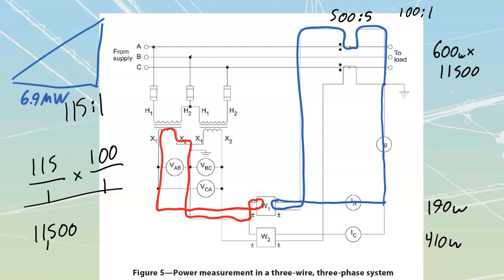Okay, now that we've got the megawatts over there, the next thing that we are going to do is figure out what our circuit power factor is. And thankfully, we have these two over here that we are able to calculate with. We can only do this calculation, though, if it is balanced. Don't try using this unless they tell you that it's a balanced load. You have to err on the side of the fact that it might not be, and you might not be able to utilize this. Because it is a balanced load, we're able to do this one where we have that inverse tangent, root 3, wattmeter 1, wattmeter 2, and all that other stuff that we can put together into a calculator.